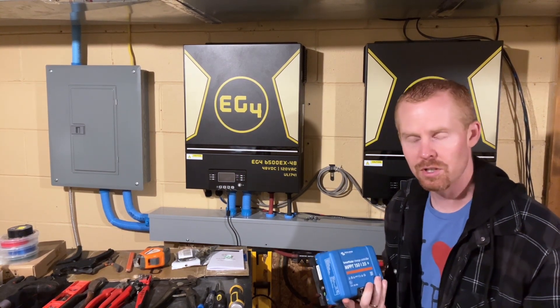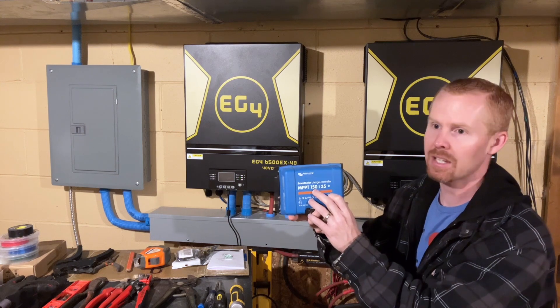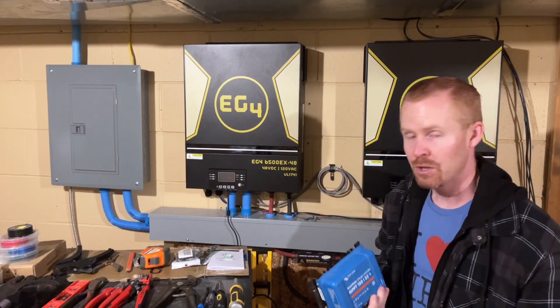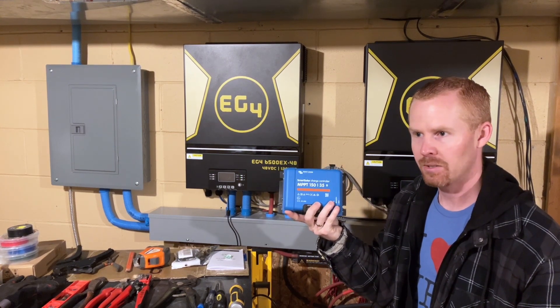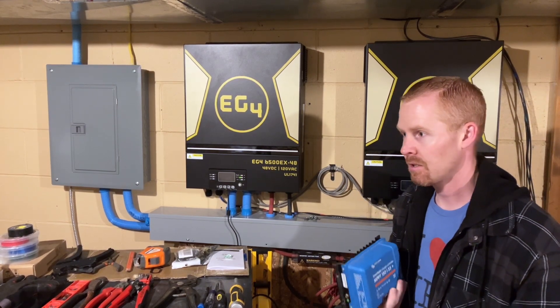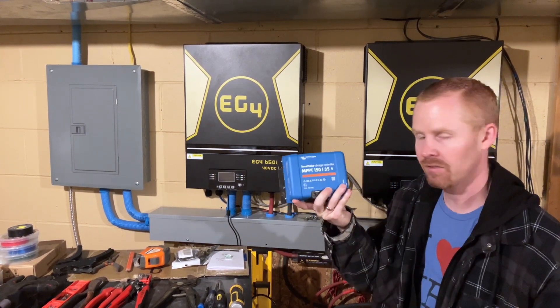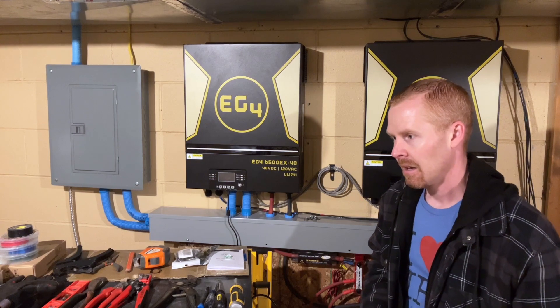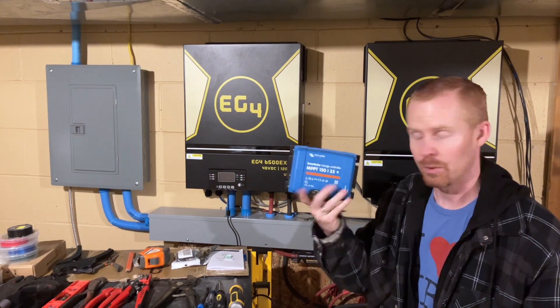The only reason I'm not using standalone charge controllers instead of the ones built into the inverters is that my panels have an open circuit voltage of 50 volts. You wouldn't want to put three in series because that would be right at the peak, and on a cool day you might get a little more than 50 volts per panel and fry your charge controller. So I'd only be able to put two on here. I have 11 panels that are 455 watts each with 50 volts open circuit, so I'd have to buy a lot of standalone units, or buy the jumbo version of the Victron, which just doesn't make sense right now. I might end up running some of my smaller 100-watt panels into these, which is why I haven't gotten rid of them yet.